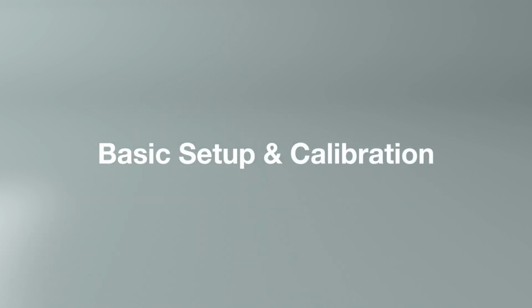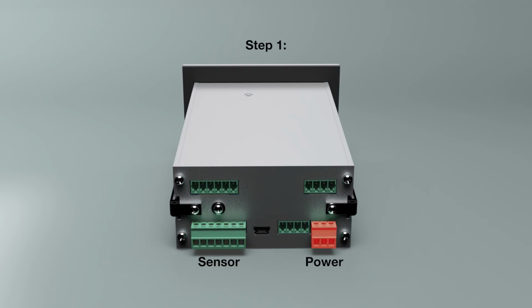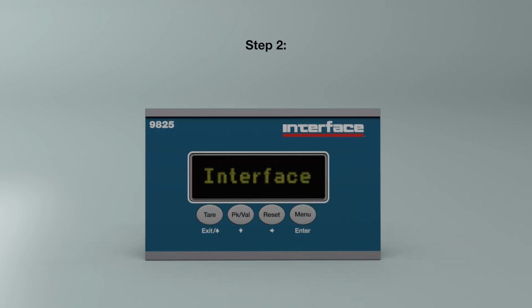Basic setup and calibration. Connect the sensor and power supply to the 9825. For details on pin assignments, refer to the basic connections for 4 and 6 wire configurations as displayed earlier in the video. Step 2. Power up the 9825. The interface logo will appear on the display. Once the 9825 has completed its startup routine, the current value will be displayed.